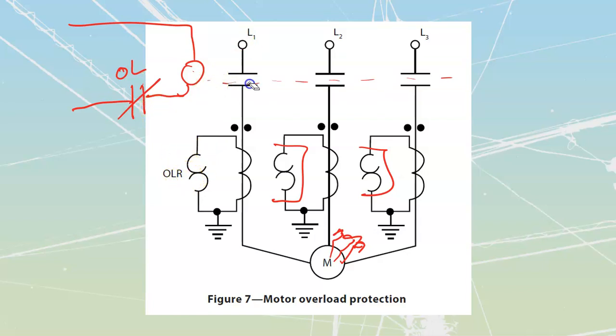Now, if it's a 500 amp motor, we don't want to be taking a 500 amp heater. First of all, it would be gigantic. Secondly, we would have a ton of heat that we'd be putting off of it all the time. So what we'll do is we will just go and get a CT. And this CT over here, if this one is a 500 to 5 CT, for every 500 amps of current that goes through, it's only going to be putting out no more than 5 amps. So I would have a 5 amp overload heater over here that I would be able to place on there. Tiny, tiny little bit of heat is going to come off of this thing, as well as it's going to be a small, cheap component for me to operate.